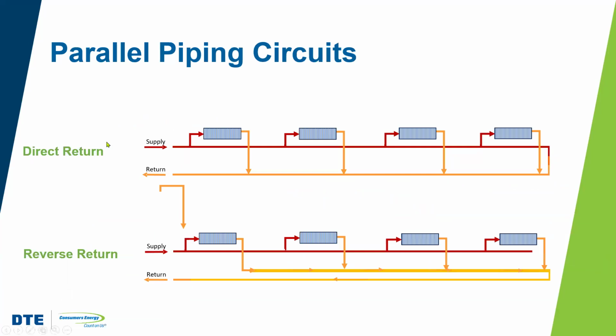So those were the series pumping arrangements. We also have a parallel piping arrangement. With parallel piping, this is more common in commercial systems, but I'll talk about it just because sometimes we do see this in large residential, multifamily residential. And so for the parallel piping systems, you've got two major divisions, direct return and reverse return.